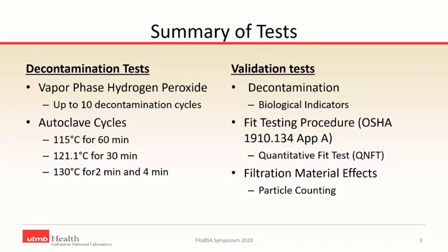And for autoclave, we used 3 different temperature sets. 115 degrees C for 60 minutes, 121 for 30 minutes, and 130 for 2 minutes and 4 minutes. The reason why we did 115 and 130 was that we were calculating to see if, with a lower temperature achieving the same lethality, we could obtain less damage to the material of the N95 mask. And also at 130 degrees, even though it was a higher temperature, because the exposure time was going to be much shorter, we wanted to see if we could get lethality and still maintain the integrity of the material.